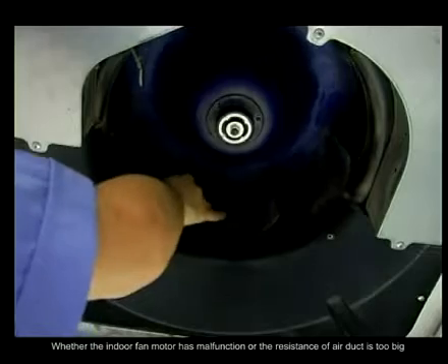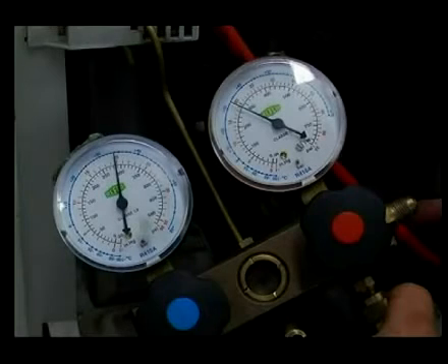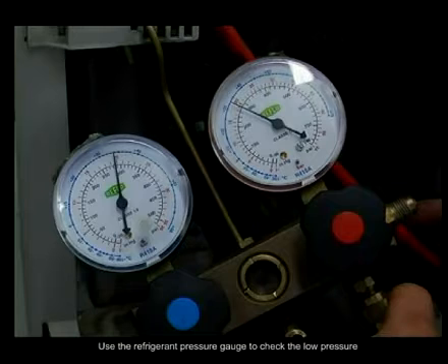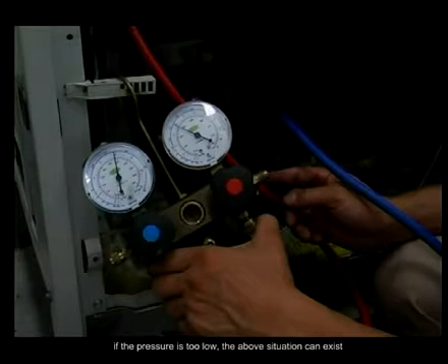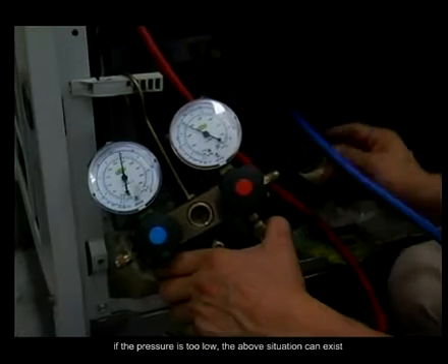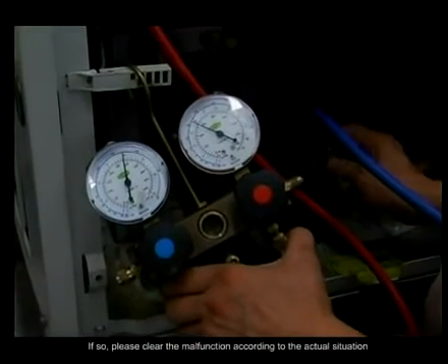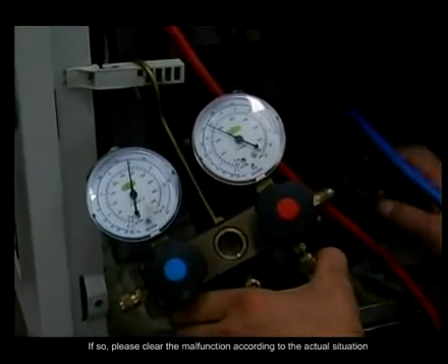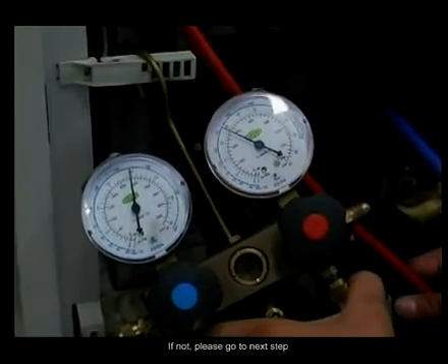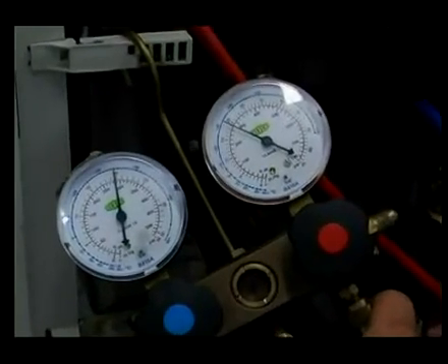Check whether the indoor fan motor has a malfunction or the resistance of the air duct is too big, which causes air volume smaller than normal. Use the refrigerant pressure gauge to check the low pressure. If the pressure is too low, the above situation can exist. If so, please clear the malfunction according to the actual situation. If not, please go to the next step. Step 2.